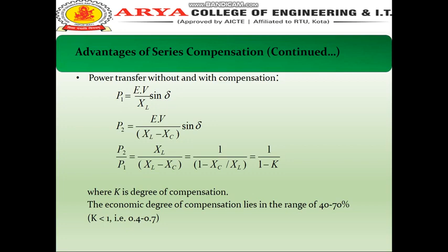Therefore, P2 upon P1 becomes XL upon (XL minus XC), which equals 1 upon (1 minus XC upon XL), which equals 1 upon (1 minus K), where K is the degree of compensation. The economic degree of compensation lies in the range of 40 to 70 percent, and K is always less than 1, that is 0.4 to 0.7.